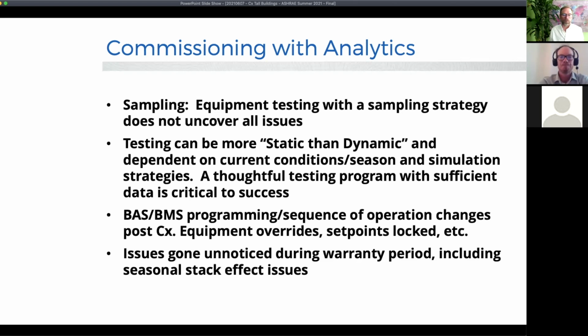So understanding that there are going to be operational changes is important. As a commissioning agent, you want to make sure you're covered, and when you hand off your final report it includes the level of detail of where you left it, what sequence you left it at. So if a set point or something has changed, you don't really become responsible for that. But hopefully you don't come into that situation if the operators have been trained, they understand, they know how to look at alarms and handle it. It definitely depends on the type of project and the skill level of the building's operators.